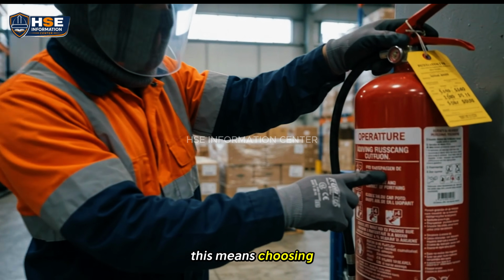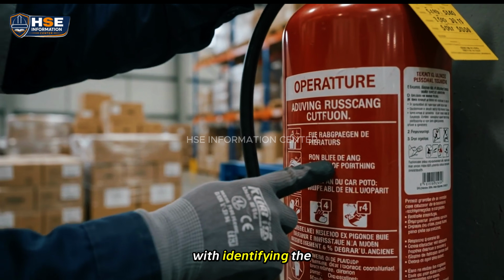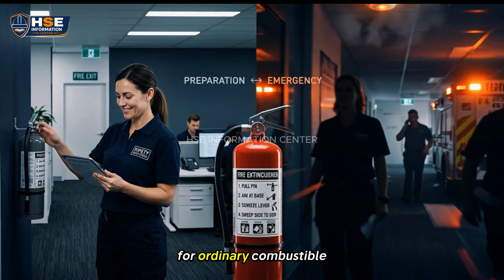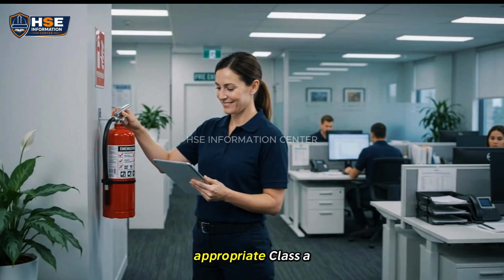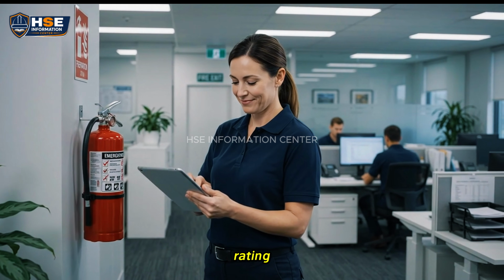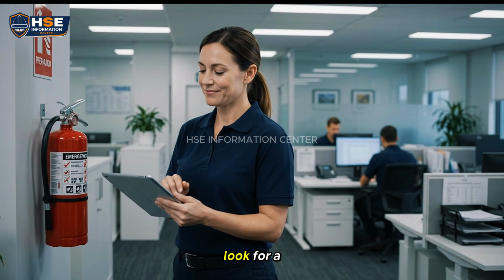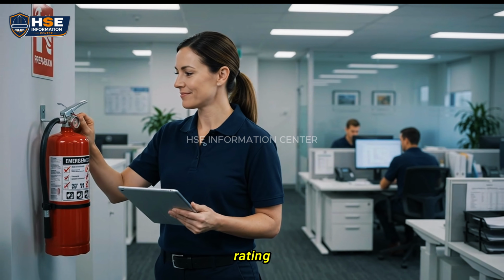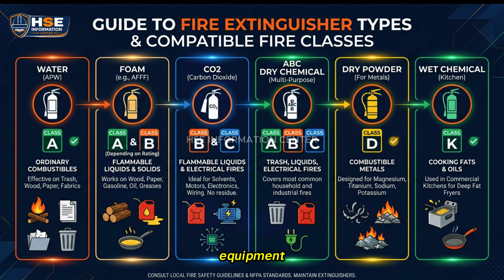This means choosing an extinguisher starts with identifying the hazard. For ordinary combustible materials, look for an appropriate Class A rating. For flammable liquids, look for a suitable Class B rating. For energized electrical equipment, select an extinguisher with a Class C rating. For combustible metals, use the correct specialized Class D extinguisher. For cooking oils and fats, use a Class K extinguisher.